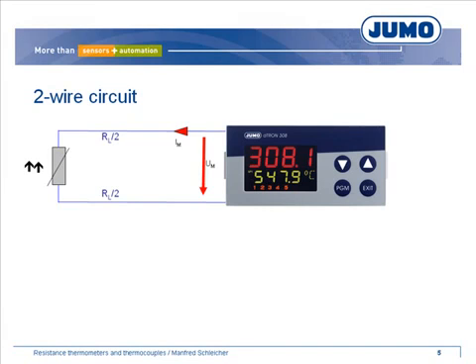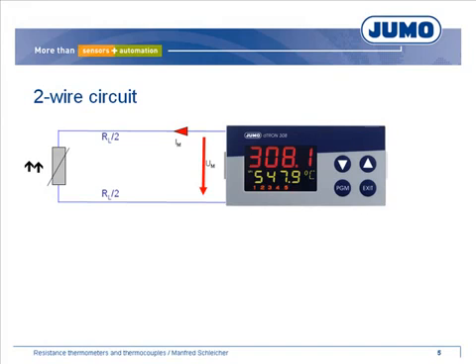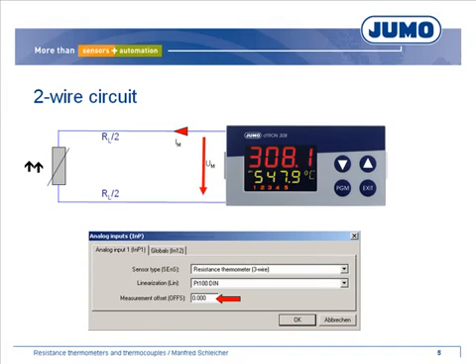Resistance thermometers can be connected to a field device in three different circuit versions. The picture shows the so-called two-wire circuit. In that case, the field device measures the resistance value of the thermometer plus the lead resistance, resulting in a higher measured temperature than the real temperature. An offset correction can be applied in the device or with the setup program, though the lead resistance will still change with ambient temperature and influence the measuring signal.